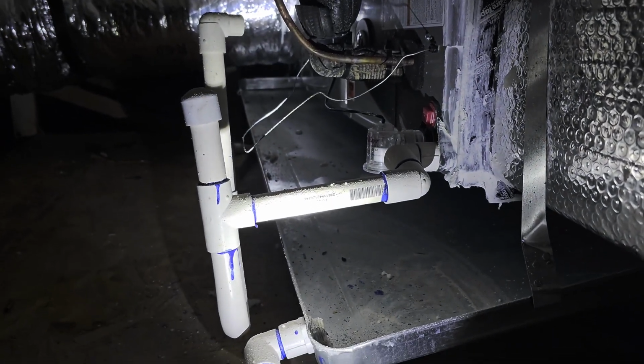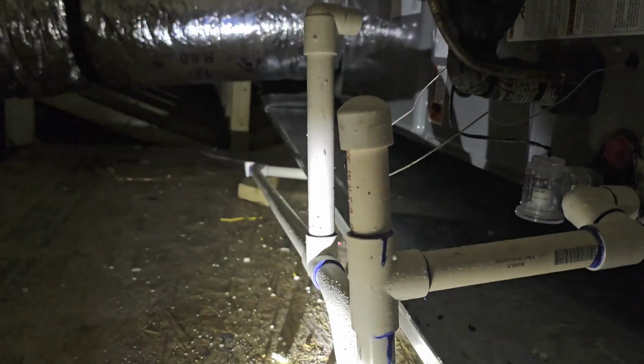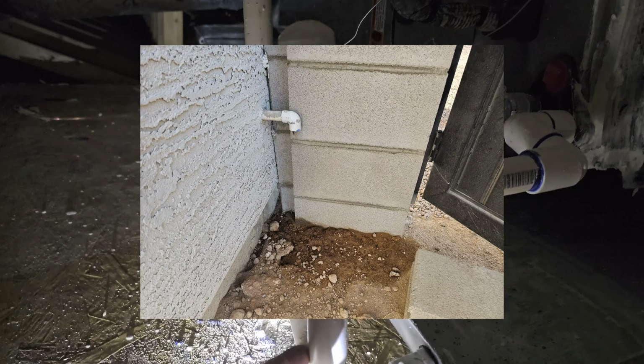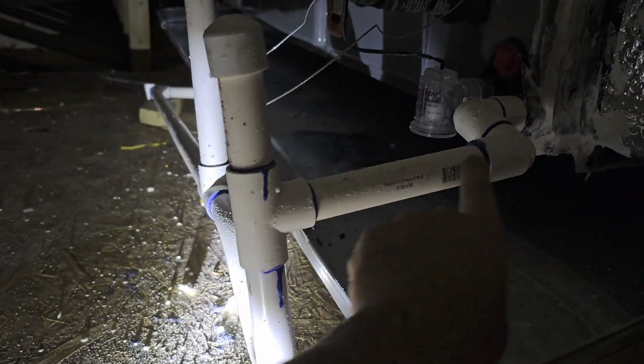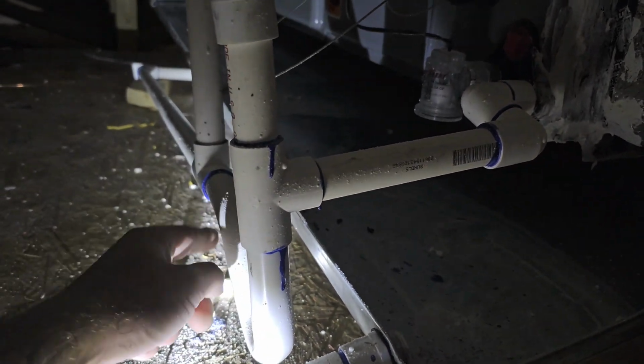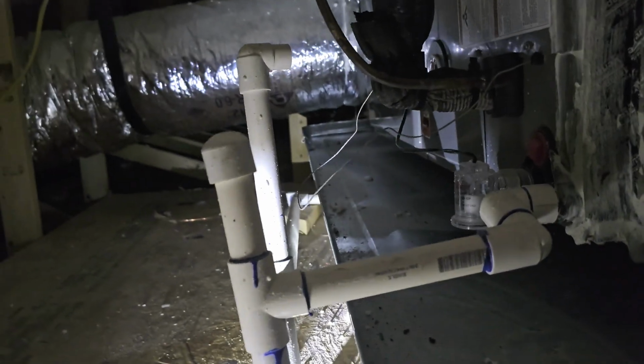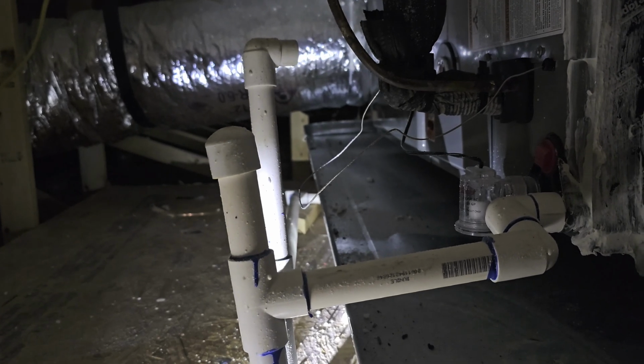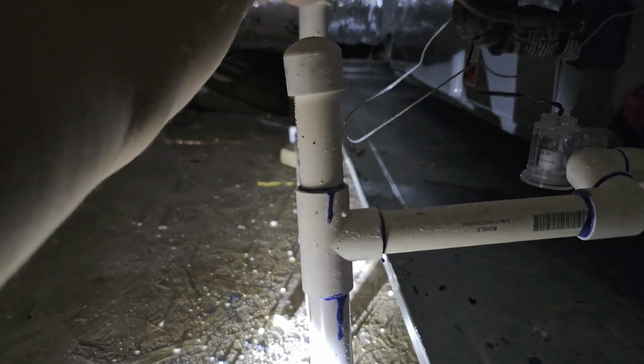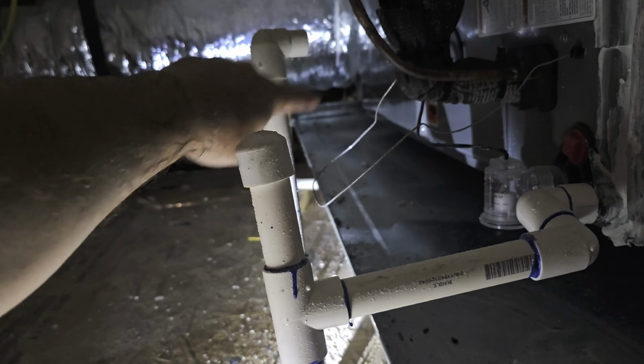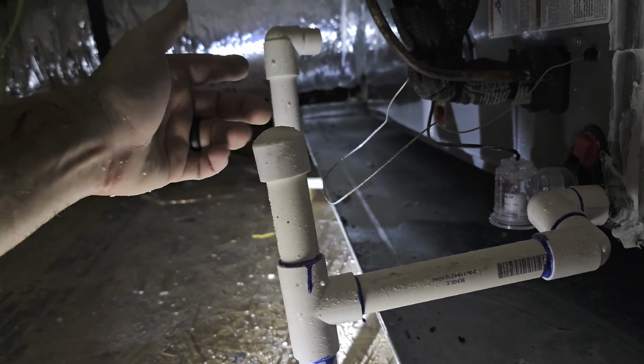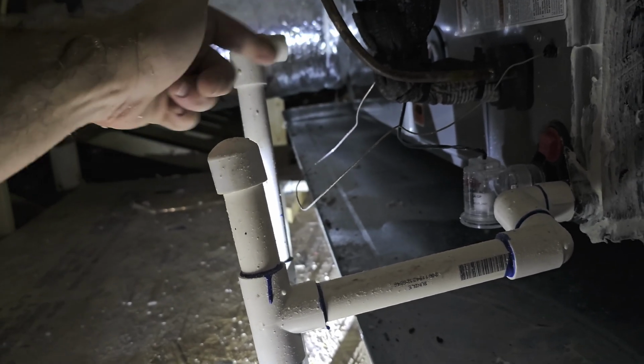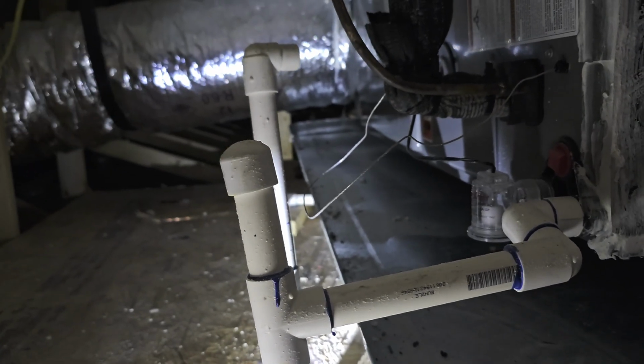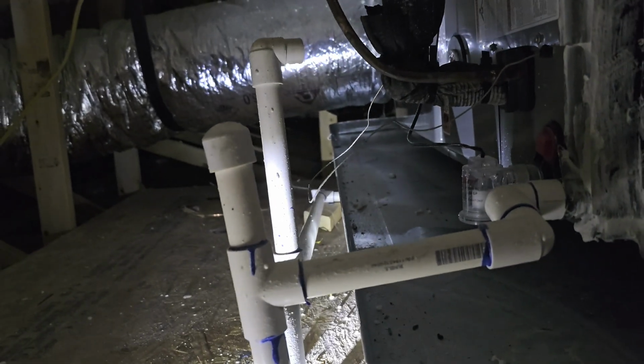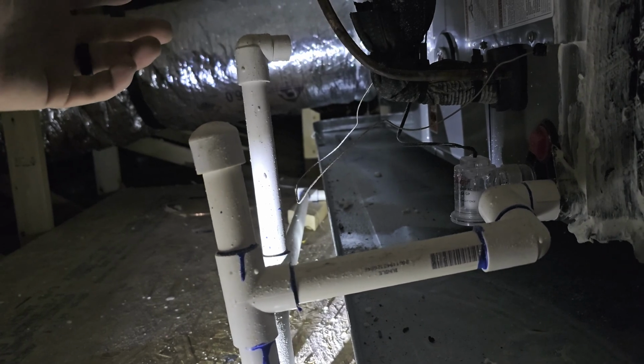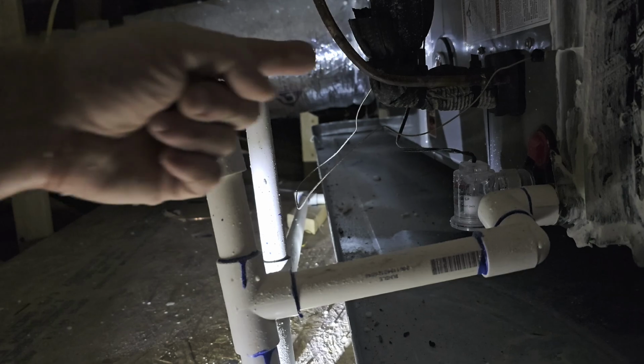Now, one thing that I commonly call out, and it's not the end of the world - say this is your primary condensate line coming out of your air handler, furnace, whatever you want to call it. You've got a P-trap, which prevents blowback, so it prevents the air from pushing all this fluid out. It's good that you have this P-trap in here. What I'm looking at is this condensate breather - they hardly ever get it over the top of the pan. They put it up so high because they don't expect it to back up and cause problems, but if it does back up and cause problems, what do you think that's for? That's to let liquid out if it does back up - condensate overflow. So why wouldn't you want that over the top of the pan? If it overflows, it's just going to go right onto the attic floor and cause water damage. So for safety reasons and water protection, get that a little bit farther. I know it's a small thing, it's 3/4 inch PVC, you could do it for 75 cents probably at Home Depot. Why the HVAC guys don't get it over that far, I don't know, but it's that easy.